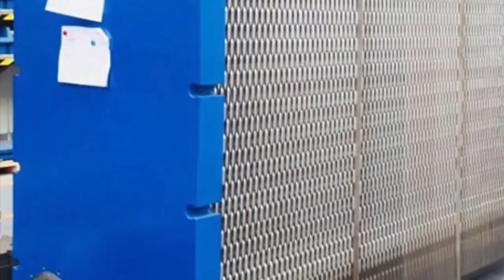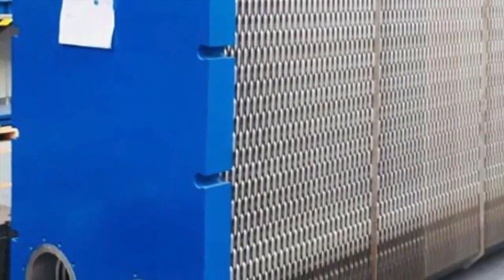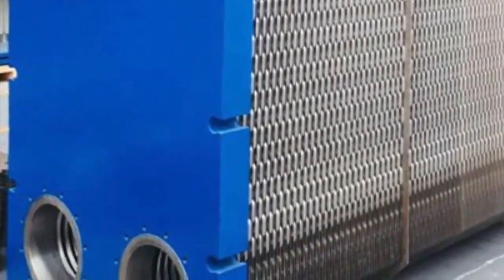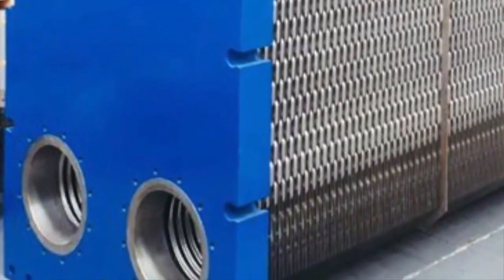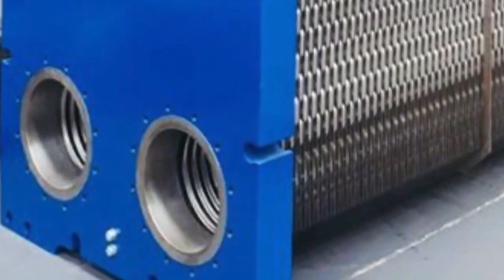The gasket of the first plate comes into contact with the circular ring of the lining. In this way, the fluid passes through the barrel, enters between the first two plates, and never touches the carbon steel. The last plate is a blind plate, so it also doesn't touch the carbon steel, but always stays between the stainless plates. Fluids don't pass between the first plate and the barrel; they enter directly between the first two plates.